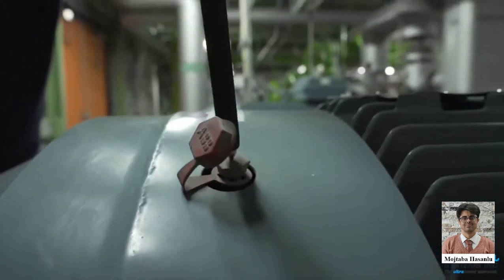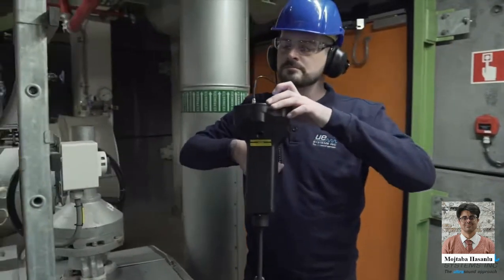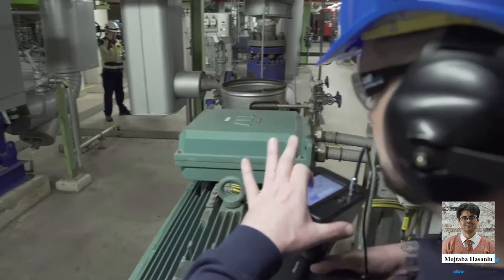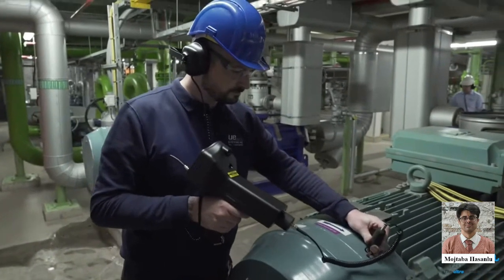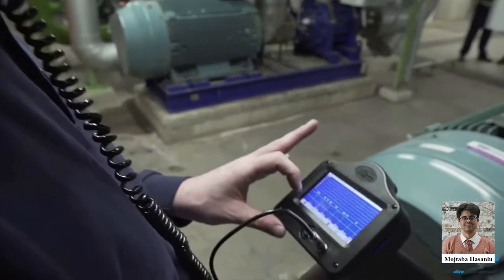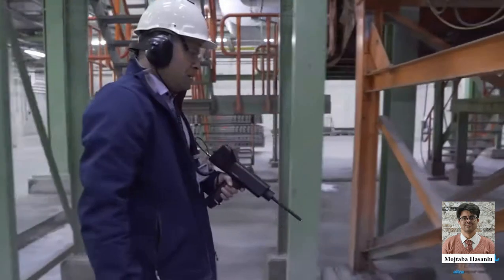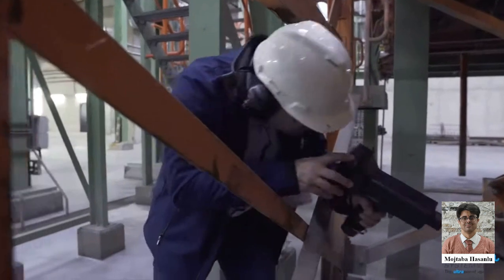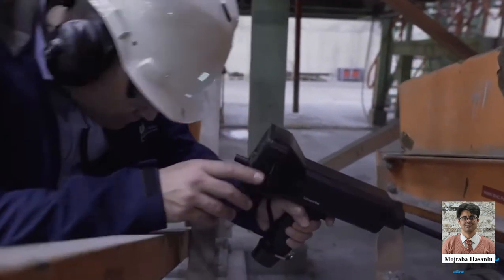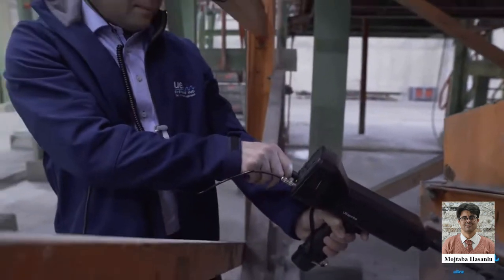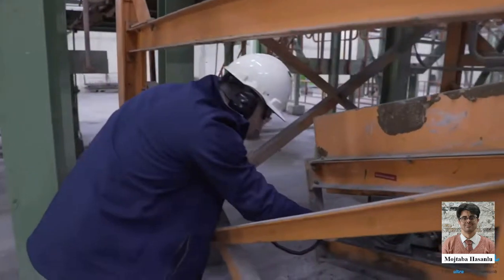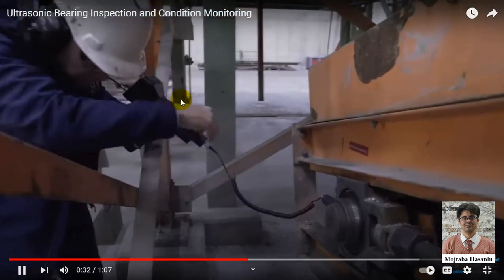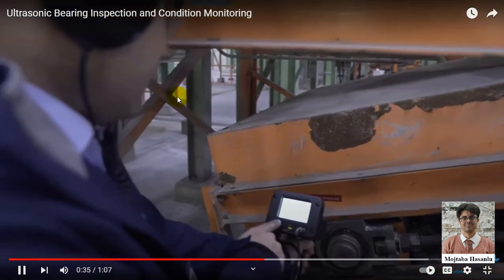Ultrasound is a very effective technology for bearing condition monitoring and predictive maintenance. You can get an early warning of failure in all bearing speeds, high, medium, or low. Establish contact between the bearing and the instrument and listen. You should hear a smooth, rushing sound. If you hear any other noises, that might indicate a problem with the bearing.